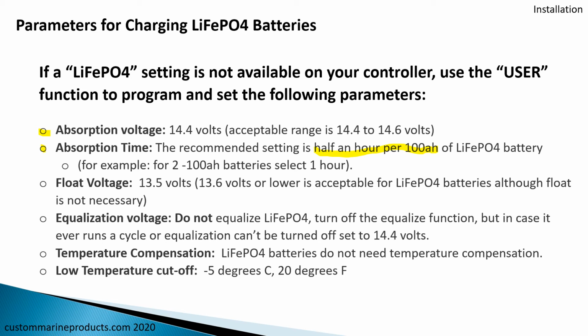Lead acid, this is often much longer, so you can use a shorter absorption time for these batteries. The float voltage, float isn't really necessary with lithium iron phosphate, but if you have a float voltage, we suggest 13.5 volts for a float. 13.6 or lower is perfectly acceptable. Your charger doing a float phase with these batteries is certainly not a problem.